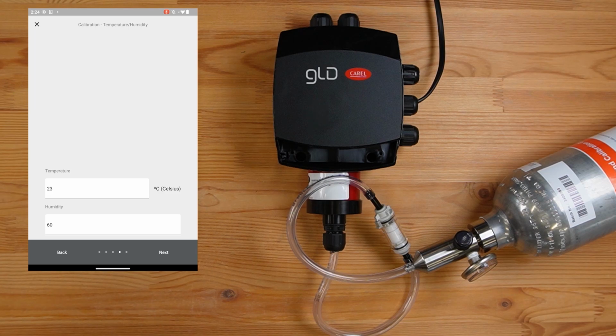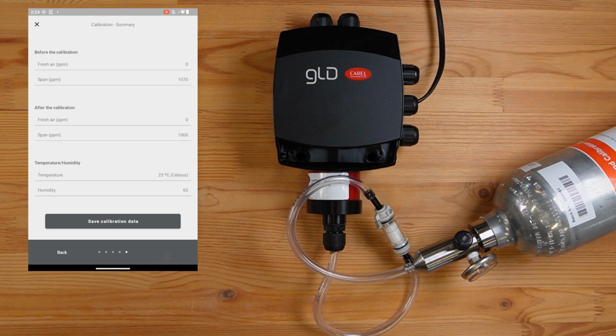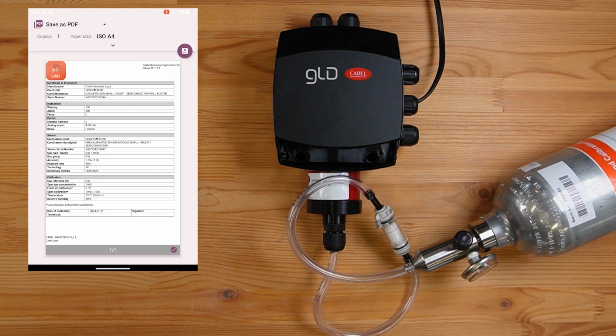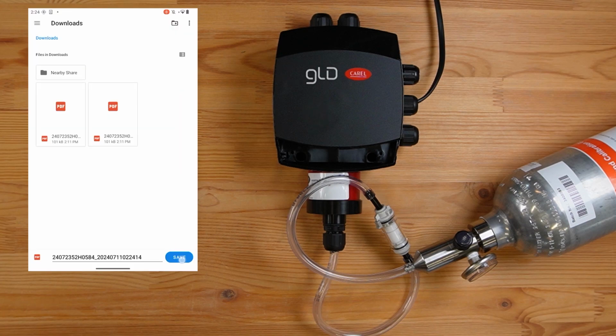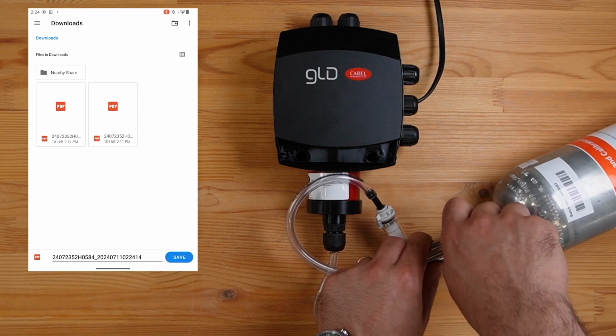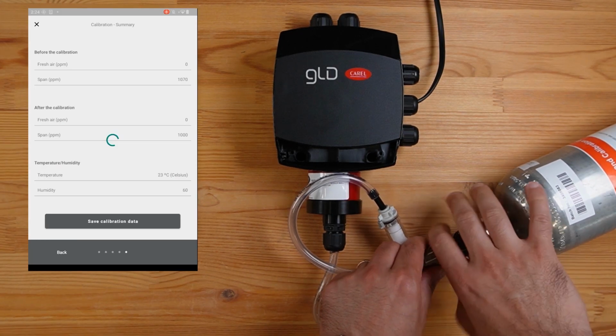These values will be entered on the calibration certificate to indicate the environmental conditions during calibration. It is not necessary to use a calibrated instrument to perform this measurement. An indicative value is sufficient. Verify the summary screen, checking that all the information has been entered correctly before generating the calibration report. Save the calibration report. Use File Manager to save it as a PDF file, or you can share the calibration report via email. You can now turn off the gas and remove the tube from the gas cylinder.